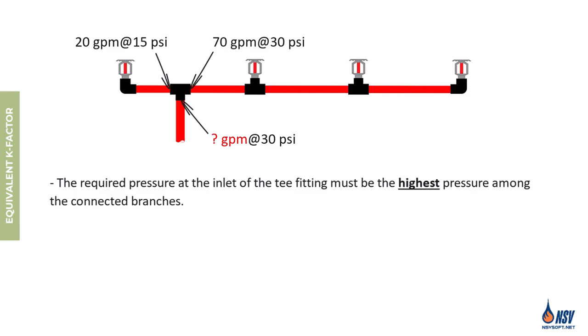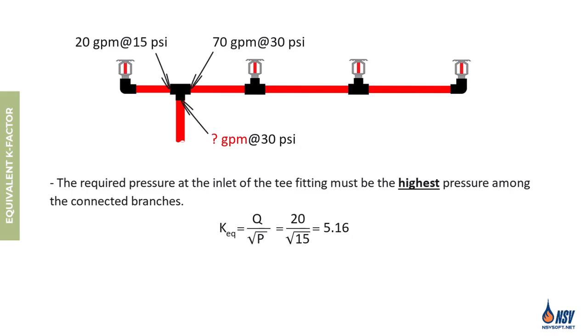By supplying 30 psi at the inlet of the tee, the three sprinklers on the right side will discharge the required 70 gpm. But the single sprinkler on the left only needs 20 gpm at 15 psi, yet we're supplying 30 psi at the inlet. This means the actual flow through that sprinkler will be higher than 20 gpm. To find the actual flow rate, we apply the concept of equivalent K factor. For the section on the left side of the tee — which includes a single sprinkler and its connecting pipe — the flow is 20 gpm and the pressure is 15 psi. Using the formula, we divide 20 by the square root of 15, which results in an equivalent K factor of approximately 5.16.